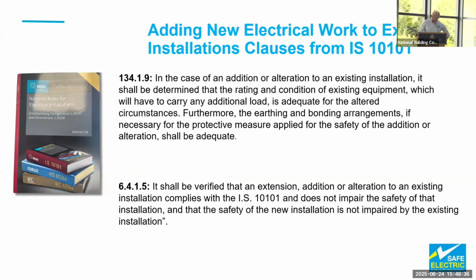The next key rule here is in chapter 6, which is to do with testing and verification. Very similar to the previous rule. It shall be verified that an extension, addition or alteration to an existing installation complies with IS 10101. What that's really saying is the registered electrical contractor has to comply with current standards every time, and that this does not impair the safety of that installation, and that the safety of the new installation is not impaired by the existing installation.